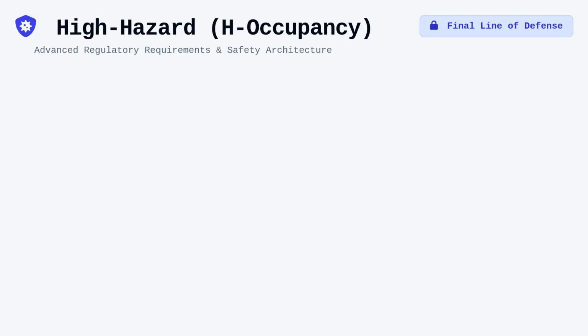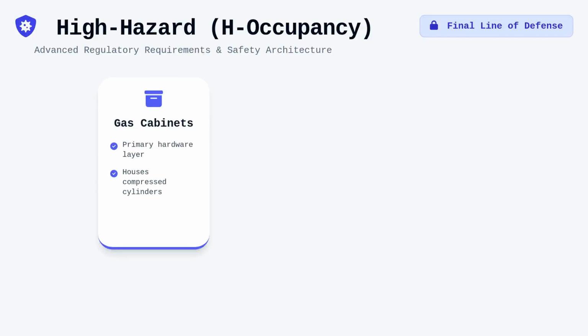When we transition to the regulatory requirements for high hazard occupancy, known as H occupancies, the level of scrutiny intensifies significantly. These facilities are designed as the final line of defense, employing sophisticated structural and mechanical enhancements to isolate hazardous events. We look at gas cabinet specifications as the first layer of hardware, which are designed to house cylinders of compressed gases and, crucially, exhaust them to a dedicated treatment system.